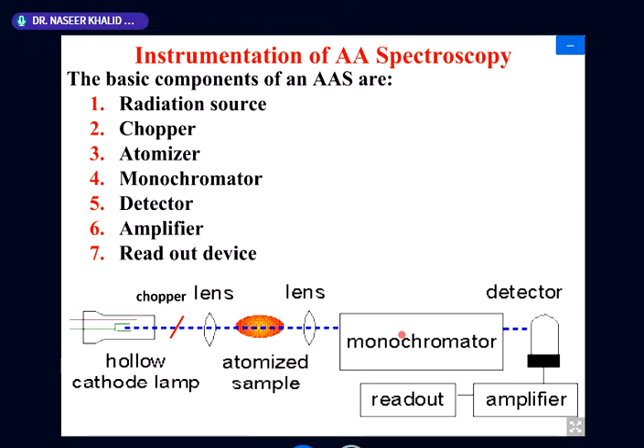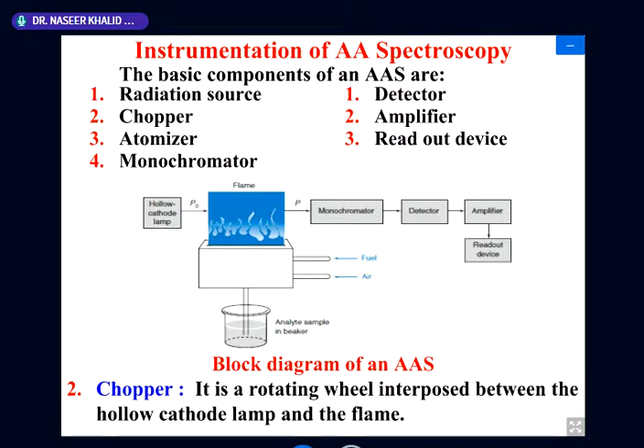When radiation passes through the flame, it is the sample beam. The chopper alternates between the sample and reference beams, giving the difference between the initial intensity and the final intensity. We differentiate between the beam that is not passing through the flame and the beam that is passing through the flame. This difference is the absorption, due to the atoms present in the flame.